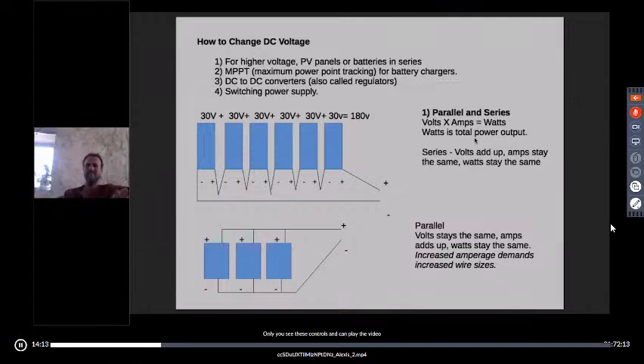If you take six nominal 30 volt panels and put them in series—as this drawing shows—you connect plus, minus, plus, minus, all the way across, until you get to the end, you have plus and minus as shown. If you do that with six 30 volt panels, you get 180 volts. Actually, on a sunny day, that's probably 230 volts, but that's okay—DC equipment can handle those kinds of voltage swings.